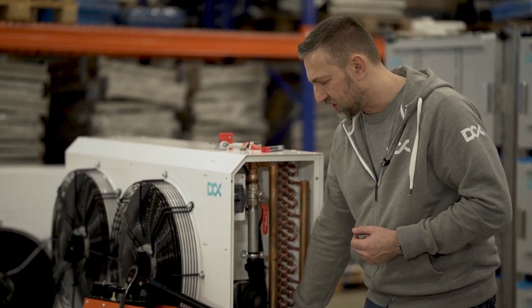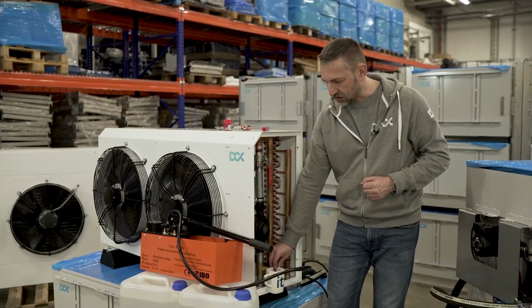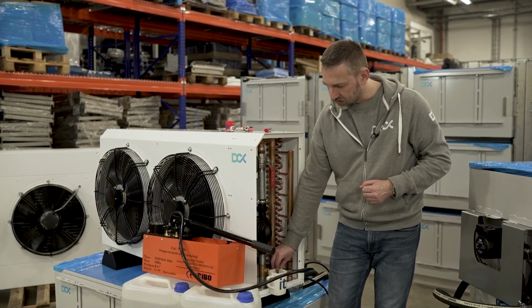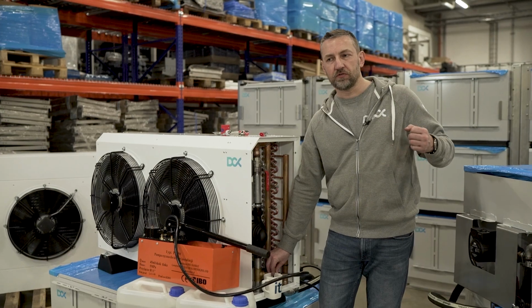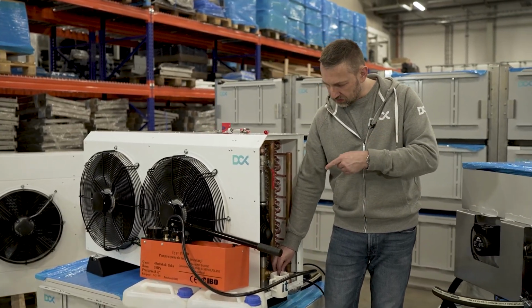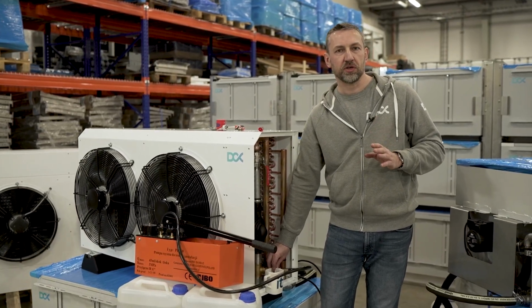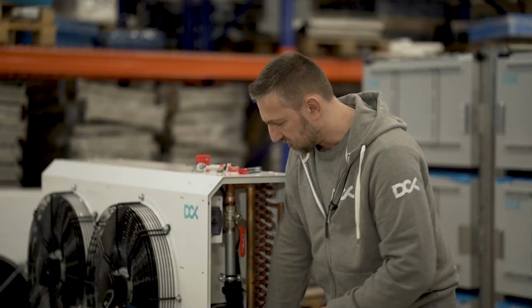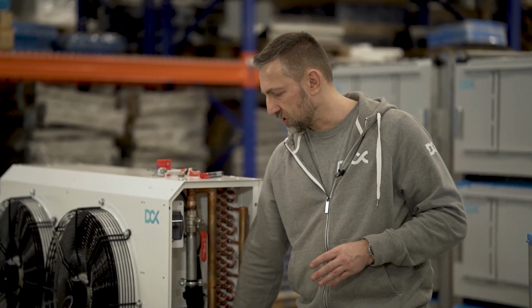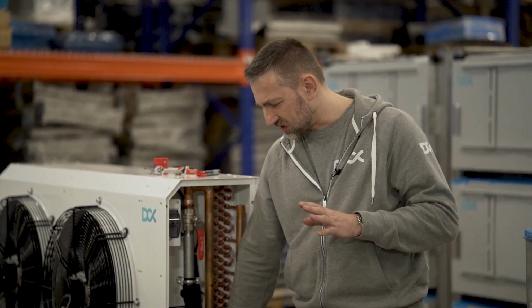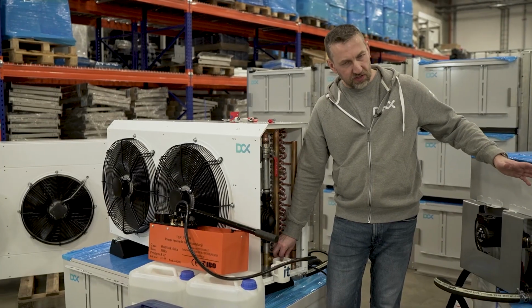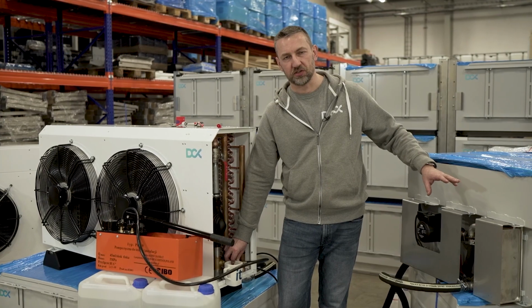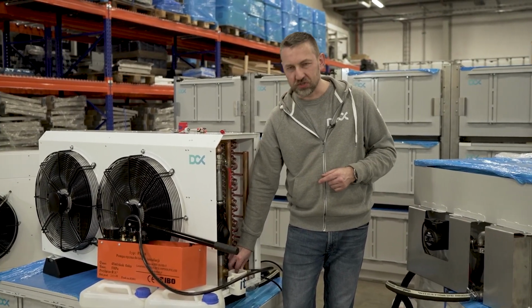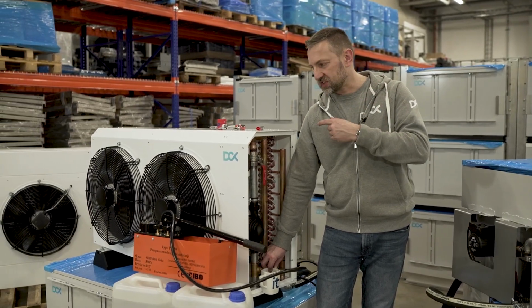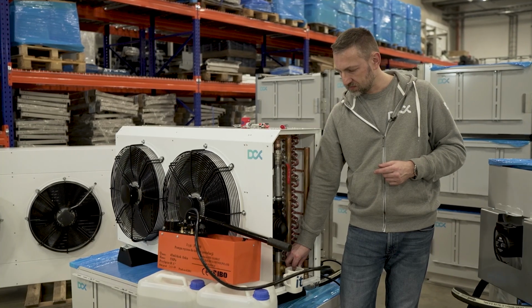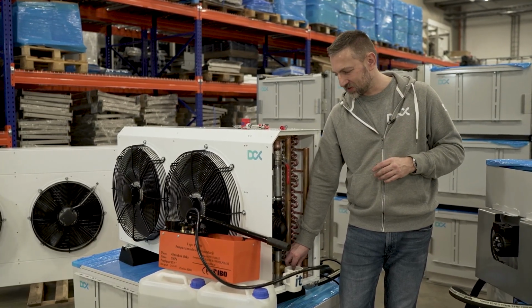You can hear that the fans are going up a little bit higher, now going to almost 55. Honestly, that's the temperature of the fluid going back from the enclosure, 56 right now. That will be a normal temperature during the moderate season or colder season, 57. That's the realistic noise of your operation during the moderate or colder season. Now 59, 60, up to 60 actually. So when it's 60 degrees, that's the noise of the operation during the hot season. And as you can see, it's almost 60, so it tries to adapt.